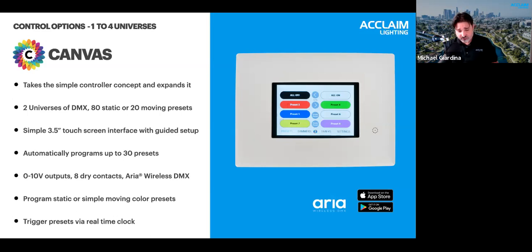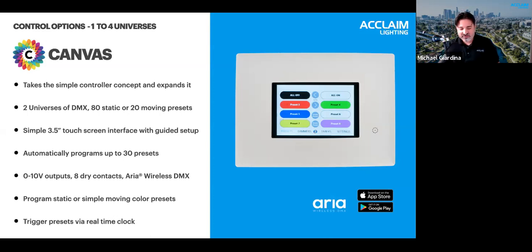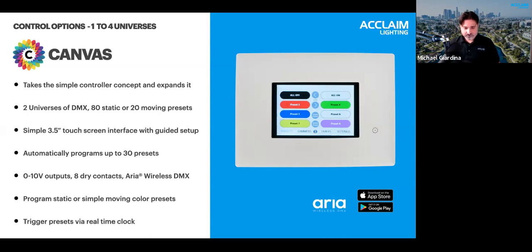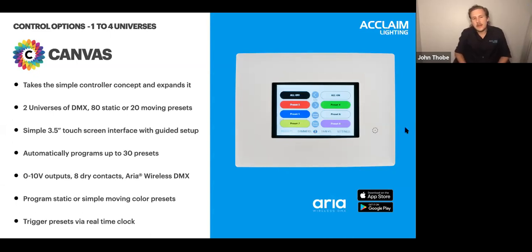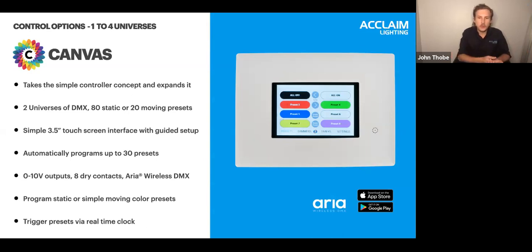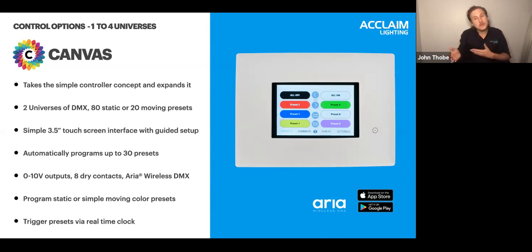Canvas features two universes of DMX as well as two 0-10V outputs, which allows you to control white light 0-10V products like our Linear One in the same programming interface as color changing units. Canvas is ideal for small to medium-sized projects needing more functionality than simple wall stations, but less than a full software-programmable controller. Importantly, it's configurable — tunable white, single color, RGBW, RGBA, and the new Spectrum Six are all options.